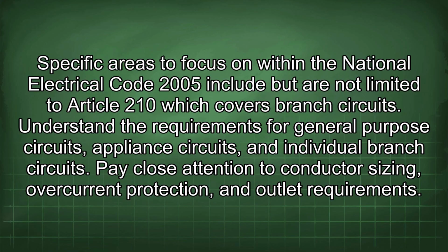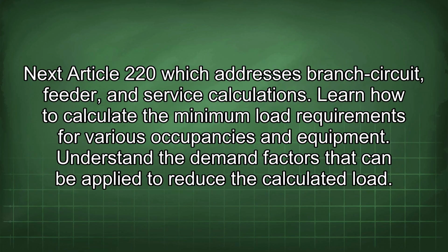covers branch circuits. Understand the requirements for general-purpose circuits, appliance circuits, and individual branch circuits. Pay close attention to conductor sizing, overcurrent protection, and outlet requirements. Next, Article 220, which addresses branch circuit, feeder, and service calculations. Learn how to calculate the minimum load requirements for various occupancies and equipment. Understand the demand factors that can be applied to reduce the calculated load.